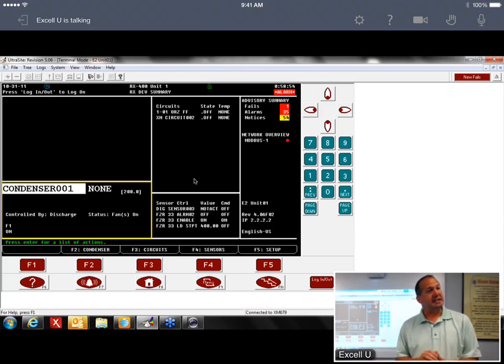You can reuse the CCB network if you're doing a case changeout and they're not going to run a new network. I've seen people reuse the same network that the CCBs use. So if you've got 2 cases going in with Dixell and everything else on that loop is CCB, go through and unplug all your CCBs and use that loop for your new Dixell devices.